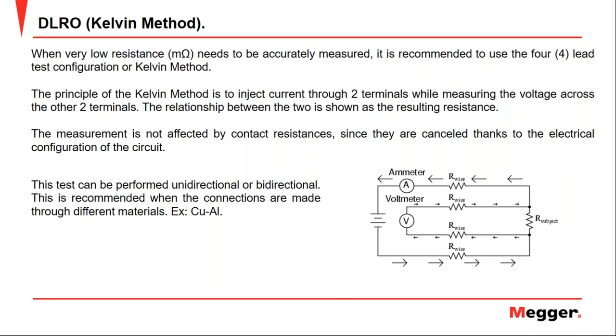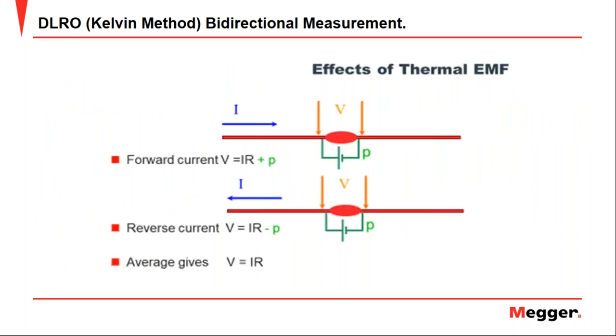For large motors, where the winding conductors' diameters are much larger, this is the method that should be used since we are talking about values around milliohms. This test can be performed unidirectional or bidirectional. Bidirectional is recommended when the connections are made through different materials. Let's take a look at the thermal effect, or the Seebeck effect.